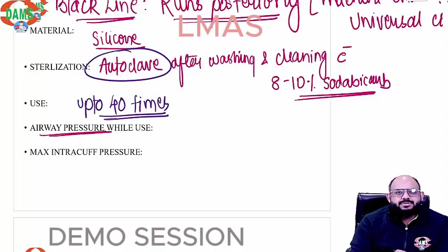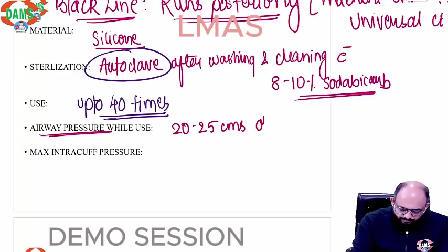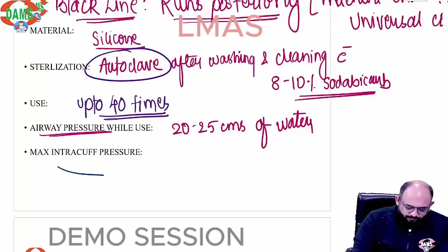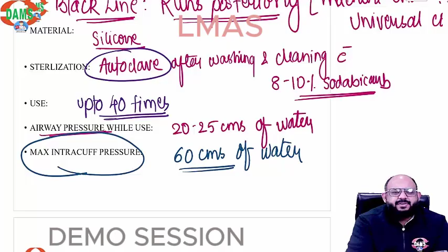Airway pressure that you can use while you are using an LMA Classic is around 20 to 25 centimeters of water. Once you inflate the cuff, the maximum intra-cuff pressure should be 60 centimeters of water, which is the maximum pharyngeal mucosal pressure. So if the cuff pressure goes beyond 60 centimeters of water, it can cause pharyngeal mucosal ischemia, which can later lead to a lot of sore throat as well as pain as well as edema in the pharyngeal cavity.